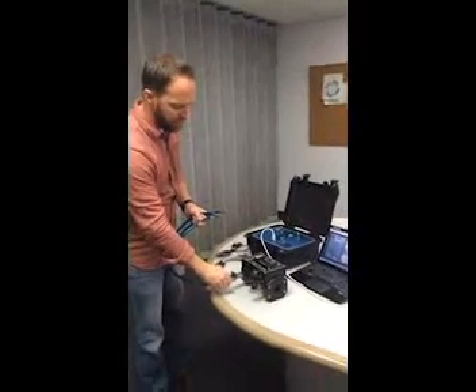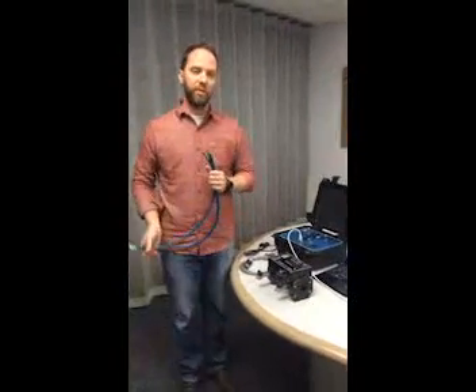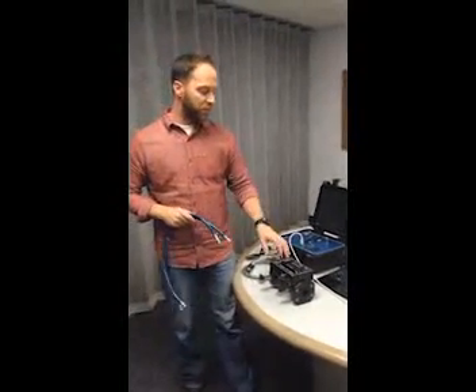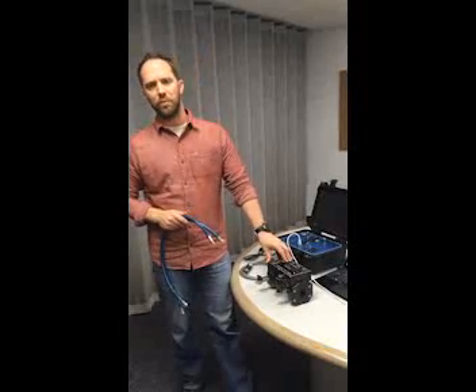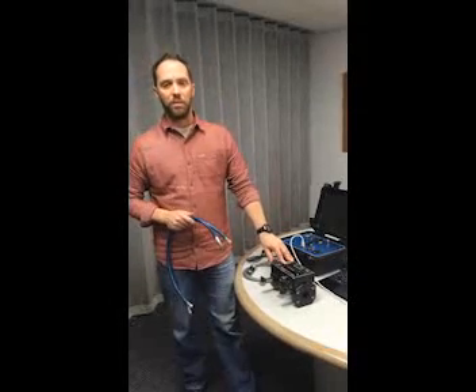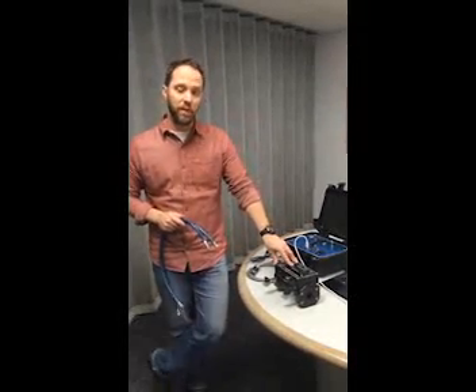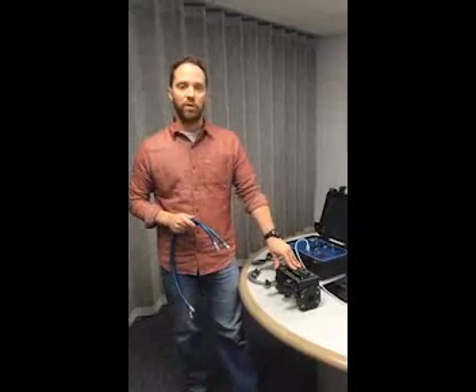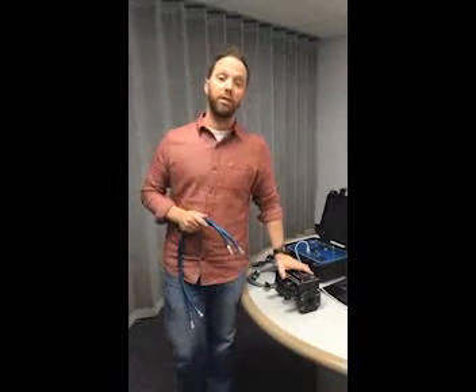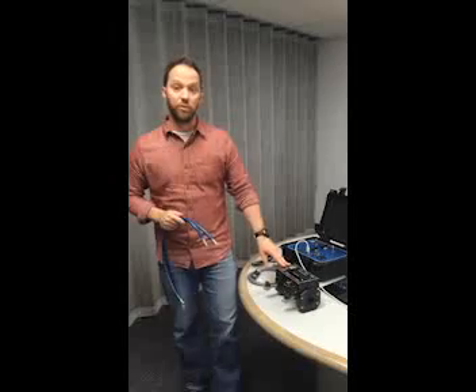Now, since we're not connecting these yet, it is worth mentioning that for the best possible calibration, you're going to zero the transducer inside the flow meter. The instructions on how to do that can be found in your FM50 instruction manual. If you don't have that manual anymore, you can go online to www.continentalcontrols.com and download those instructions as well.